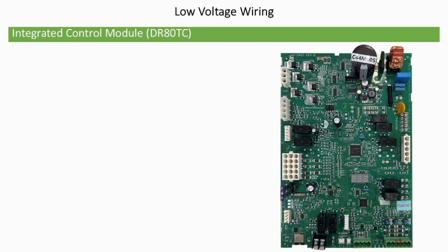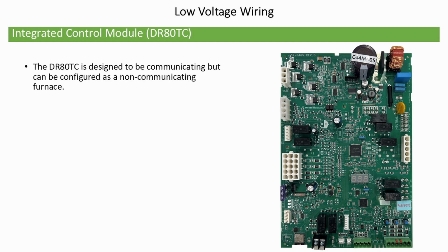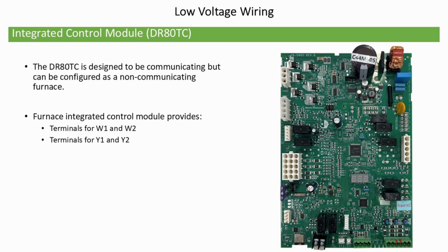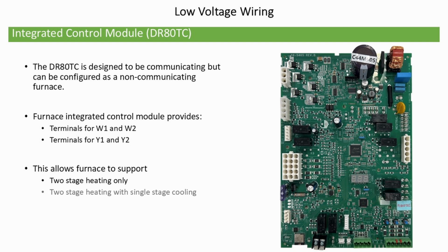Low voltage wiring. Here's a look at the integrated control module for a DR80TC. The DR80TC is designed to be a communicating furnace, but it can be configured as a non-communicating furnace. The furnace integrated control module provides terminals for W1 and W2, and terminals for Y1 and Y2. This allows the furnace to support 2-stage heating only, 2-stage heating with single-stage cooling, and 2-stage heating with 2-stage cooling.